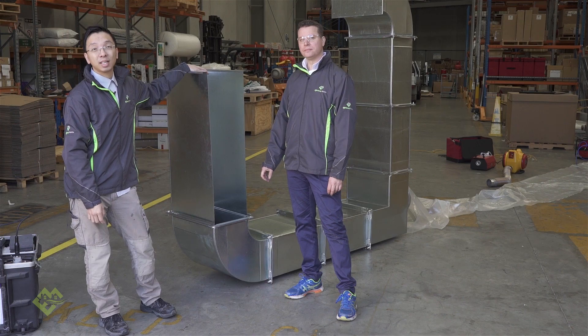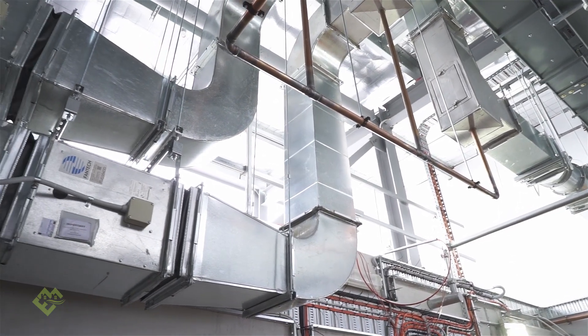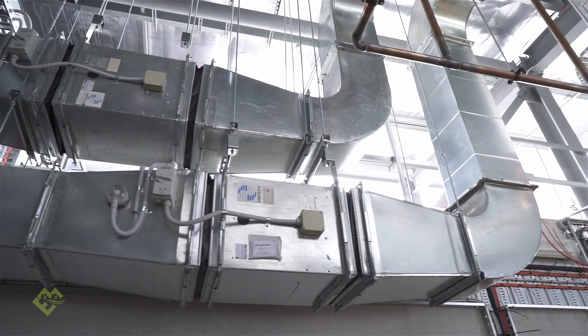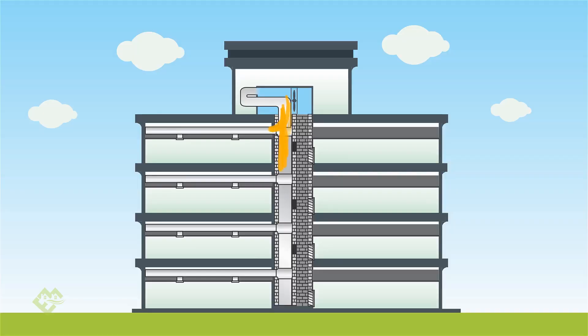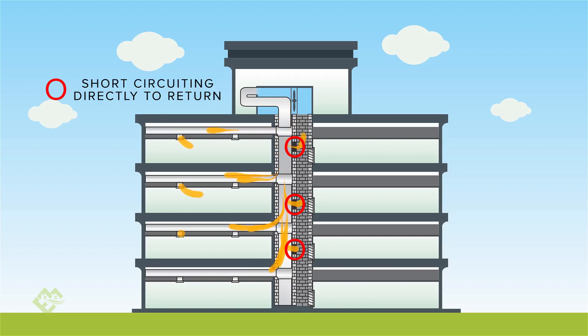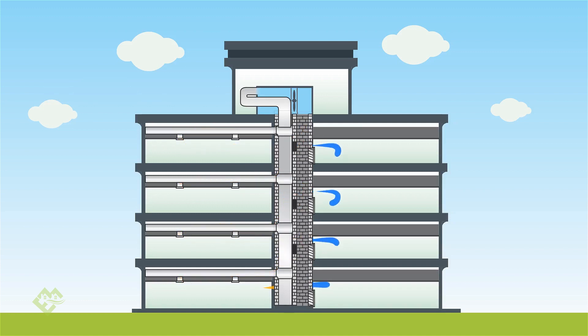In addition to wasting 35% of your conditioned air, duct leakage also disrupts your control system because you don't know where the conditioned air is leaking to. In some cases it may leak to the return air directly, which interferes with sensing and control. The thermostat inside the room may tell you that you need more cooling, but the return air temperature sensor at the air handling unit tells the system it's already cold enough — giving conflicting signals that the control system simply doesn't know how to handle.